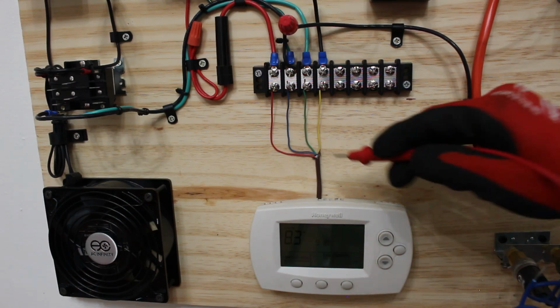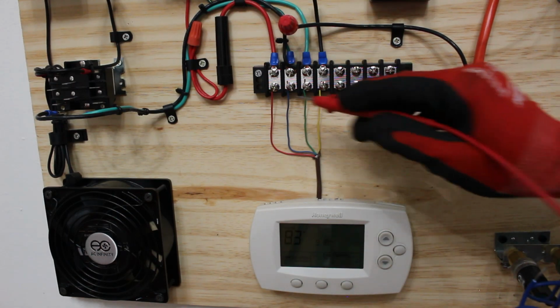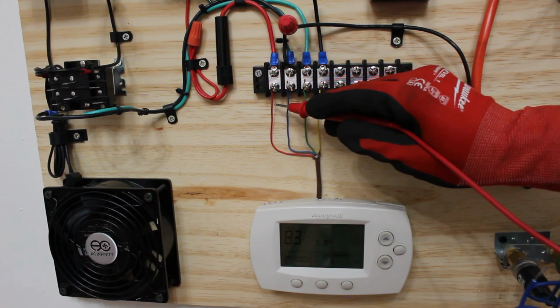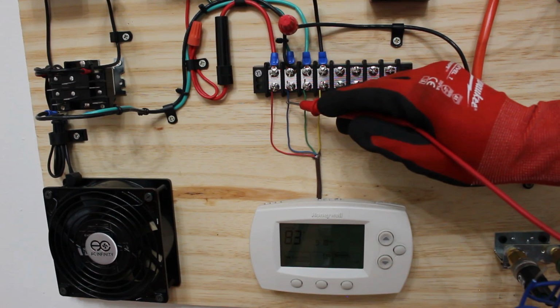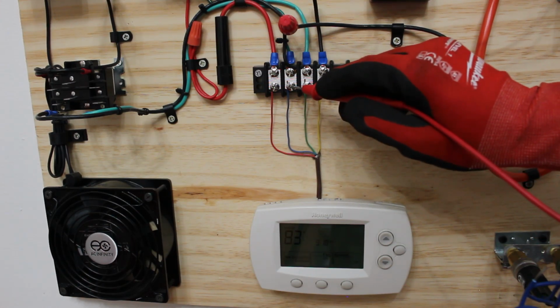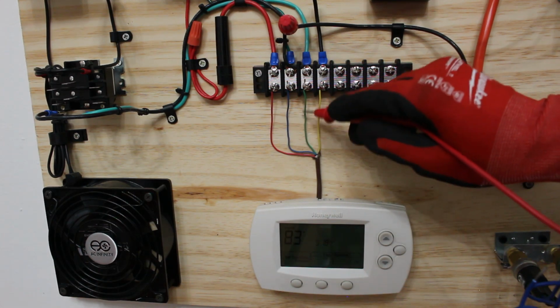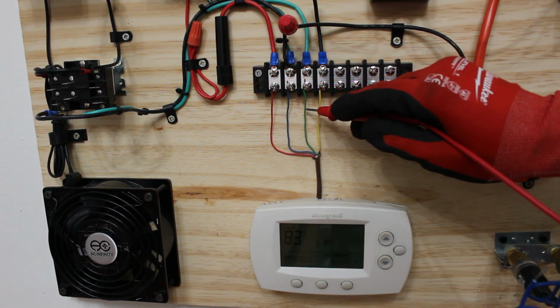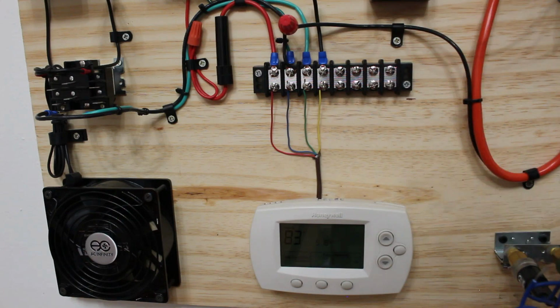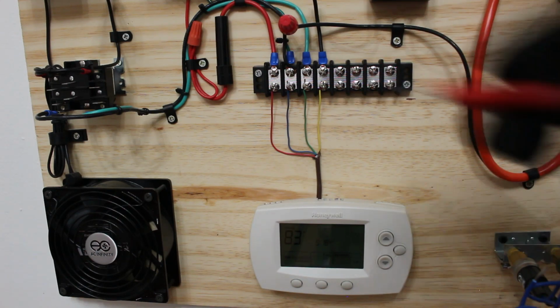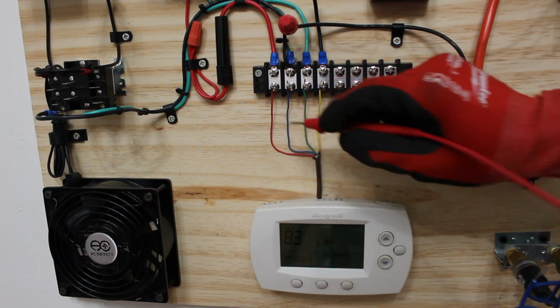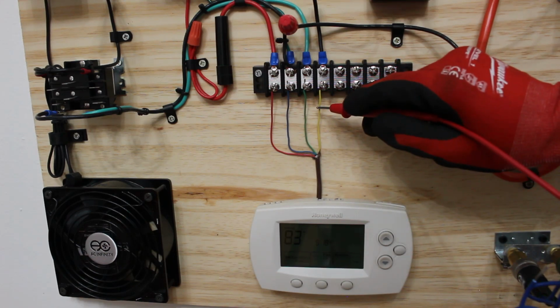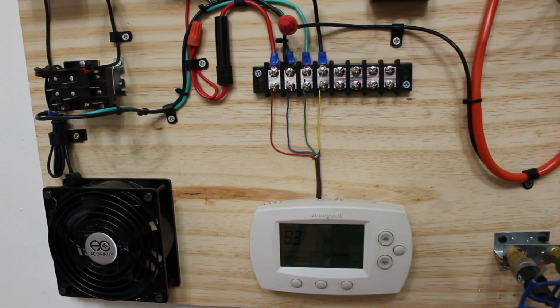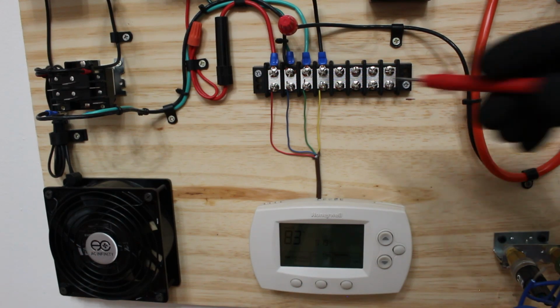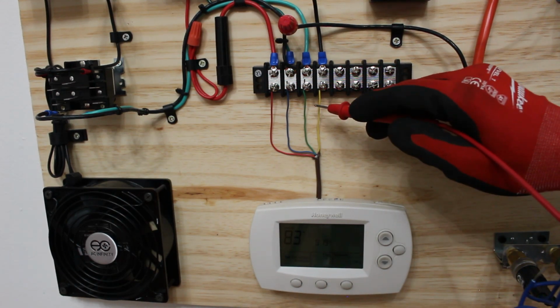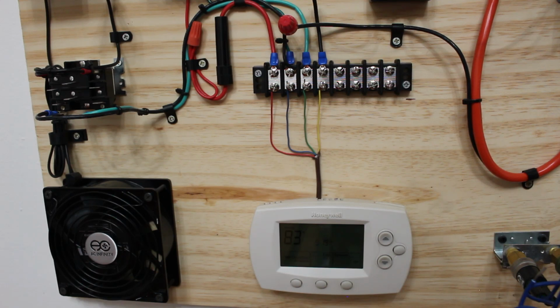Here is our thermostat. Here's our thermostat cable. We have a red wire, which is our 24 volt supply. We have a blue wire, and this is our common. Our green wire is for our indoor fan, and our yellow wire is our cooling wire. R, C, G, and Y. The best way to go about this would definitely be to make and break our yellow wire, our Y terminal, which is our cooling wire.